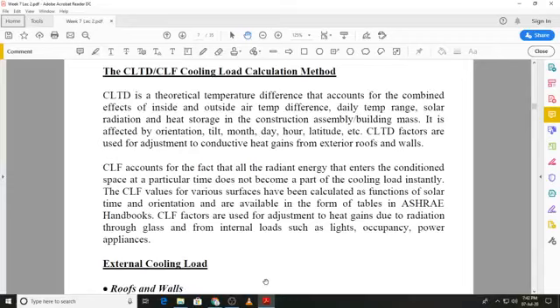However, modern-day software for calculating cooling loads uses a different cooling load estimation method, the heat balance method, for example. But that requires the solution of a large number of equations in an iterative manner, and that is suitable for computer-based solution. Manually, the method that we are going to go through is the CLTD CLF cooling load method. The CLTD stands for cooling load temperature difference, whereas CLF stands for cooling load factor.